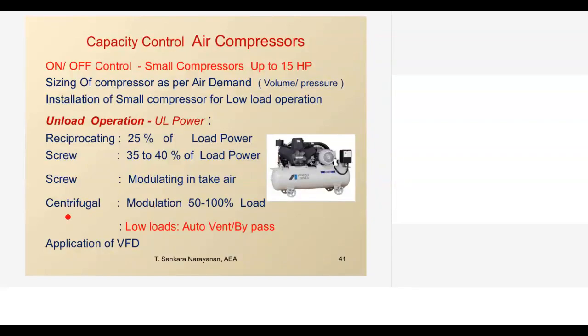So one criterion, whenever we are using a centrifugal compressor, it has to be operated for the base load. For a fluctuating load, you can have a screw with VFD or a reciprocating compressor. Centrifugal is a high capacity compressor. It has to be operated at full load only. So in any part load operation, there will be an efficiency drop.